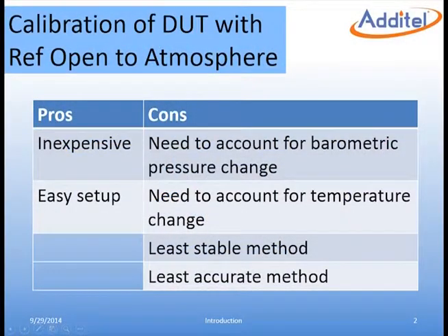In this method, the setup is very simple and the equipment used is relatively inexpensive. However, this method has some considerable disadvantages. First, because the low or reference ports are open to atmosphere, the change in barometric pressure needs to be accounted for. Depending on the calibration environment, this error can be significant. The influence of temperature effects also presents a challenge with this method. This is the least accurate method of calibration.